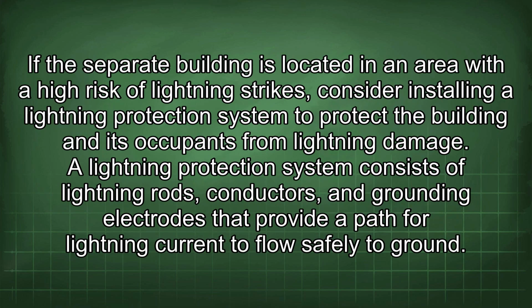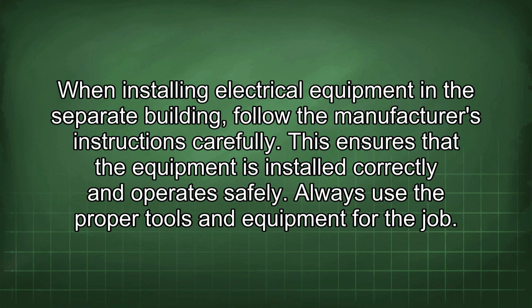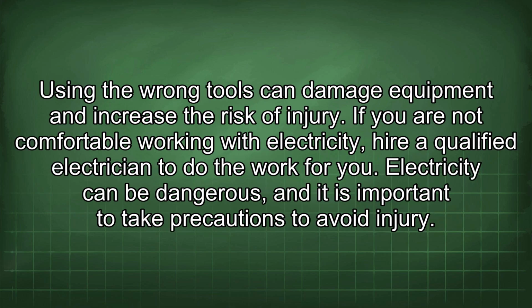If the separate building is located in an area with a high risk of lightning strikes, consider installing a lightning protection system to protect the building and its occupants from lightning damage. A lightning protection system consists of lightning rods, conductors, and grounding electrodes that provide a path for lightning current to flow safely to ground. When installing electrical equipment in the separate building, follow the manufacturer's instructions carefully. This ensures that the equipment is installed correctly and operates safely. Always use the proper tools and equipment for the job. Using the wrong tools can damage equipment and increase the risk of injury.